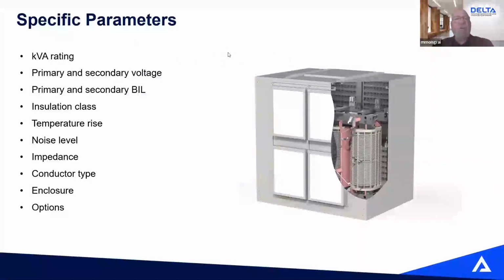So we need to know what's the kVA rating we need to replace. Do we keep the same? Do we go larger for demand? What are my primary and secondary voltage and BIL level? The insulation class of the transformer, usually it's 220. Some older transformers can have a lower insulation class.